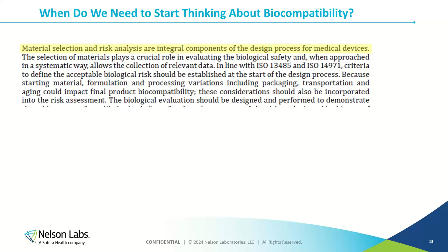But I have to say, please do not make biocompatibility an afterthought. Even though it says we need to do it at the final finished state, the concept of biocompatibility needs to be taken into consideration before the final finished state has been achieved. That is even mentioned in ISO 10993-1 as well. It says material selection and risk analysis are integral components of the design process of medical devices, right? So really, it should be a design process criterion already at the material selection part.